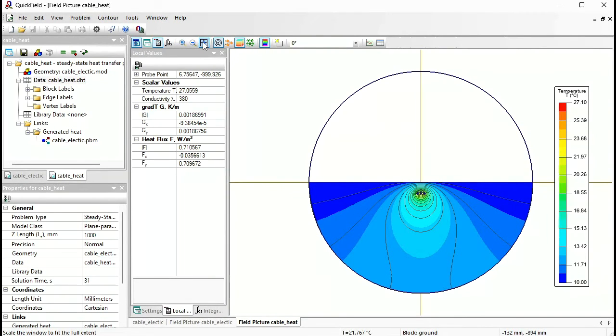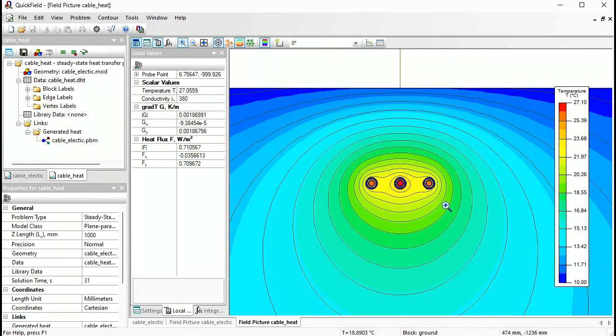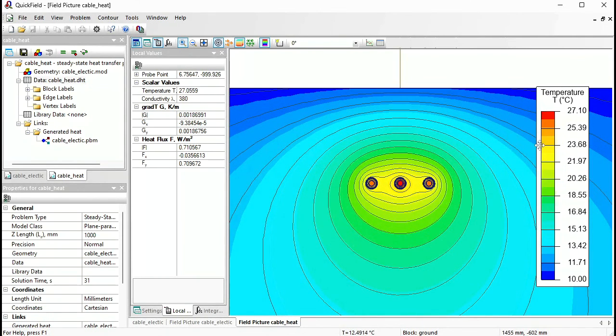Here you can see the temperature distribution. This is the temperature distribution in the ground. When the cables are energized, they are connected to the voltage source, but the load is not connected. This temperature rise is caused only by the dielectric losses in the cable insulation.